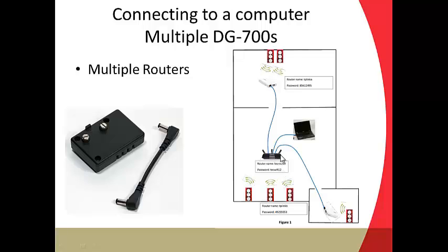But the main router was communicating with three fan systems. The back one, we had line of sight. For best case scenario, you want line of sight between where the router is and where all the gauges are, and we were able to do this test flawlessly. It's not really wireless. There are still wires, but you still end up running a lot less cabling to make this work.